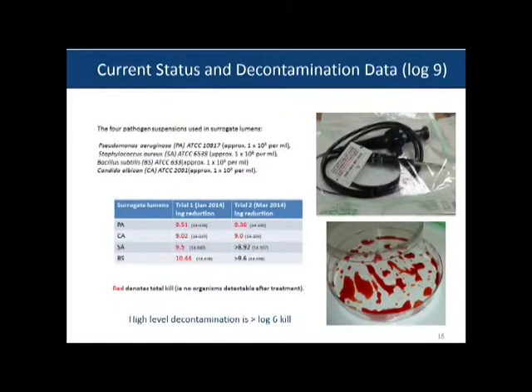So as I say, we've gone on. We have done a lot of work in testing endoscopes and taking the lumens, the very narrow pipes that go through a flexible endoscope, testing them against a wide range of fairly nasty bugs. And we've demonstrated log 9 kill. Anything greater than a log 6 kill is a high level of decontamination. With log 9, 10, 11 kill, you're getting to endpoint sterilization. So in food, we're decontaminating. In some medical devices, it's high-level decontamination, and at some point, it's endpoint sterilization. And we can change our ozone process to fit those different categories.